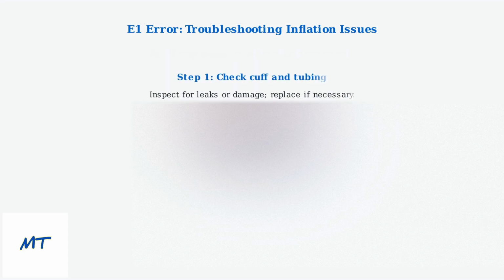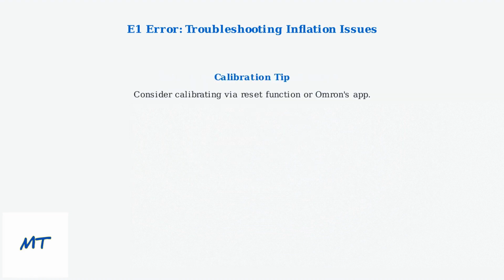An E1 error indicates that the cuff is not inflating properly during blood pressure measurement. First, check the cuff and tubing for any leaks or damage. If you find any issues, replace the components. Ensure you're using fresh alkaline AA batteries, as low battery power can prevent proper inflation. If needed, try manually re-inflating the cuff to get it working again. Finally, consider calibrating your device using the reset function or Omron's app for optimal performance.